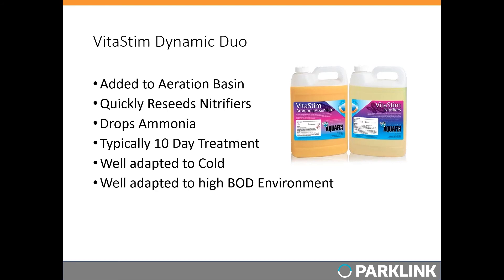Beyond six months there is some slow drop off in active concentration, but operators have reported refrigerating them for a year and still achieving great results. Two key things are kept in mind when culturing these bacteria specific to wastewater: first, they must be well adapted to a high-BOD environment — nitrifying bacteria from an aquarium fish store are not suited for high-BOD environments and would die quickly. Second, the nitrifiers are made more cold-adapted than general products, since operators often have their biggest issues during winter.